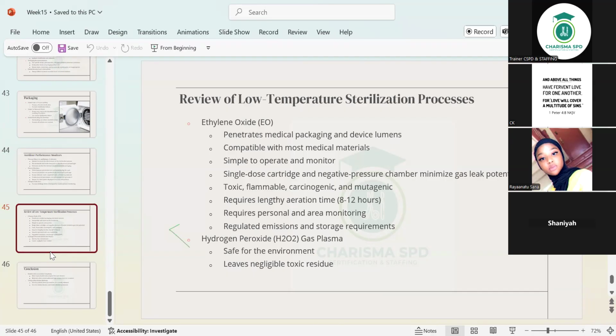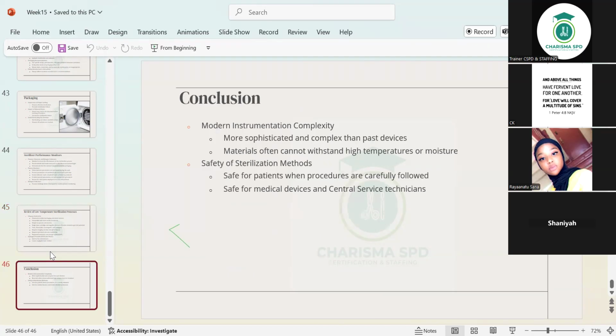All right. Then the hydrogen peroxide, the H2O2. In practical terms, when you're writing, the 2 is written below the H, and the 2 after the O is also written below the O, okay? All right, the gas plasma. It's safe for the environment. It leaves negligible toxic residue, which is very good, all right? But then, looking at all this, the ETO, the vapor, and the ozone, I said 4 hours. Look, the ETO needs 8 to 12 hours for aeration. So you see that time is a factor in here.